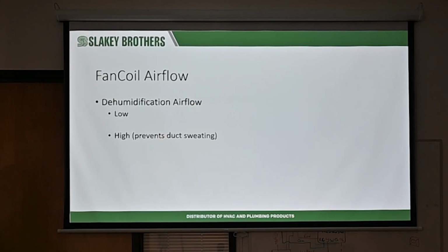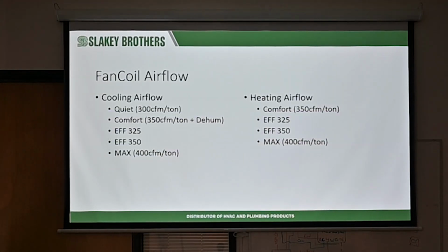So if you do enable dehumidification, you can actually tell it what to do. Excuse me, can we go back to, so if we adjust airflow, we can choose between quiet, comfort and max. That means CFM per ton, right? Yes. Whereas before you had the dip switches for the CFM, plus a couple dip switches that go from 350 to 400 CFM per ton. So there's a couple. I mean, the simple way is with the dip switches.